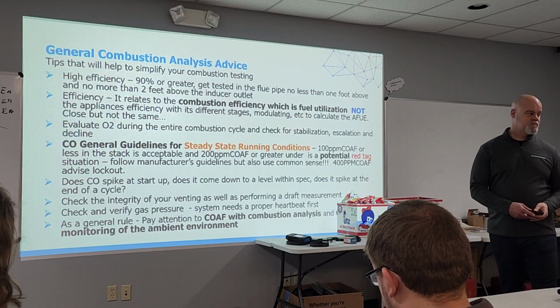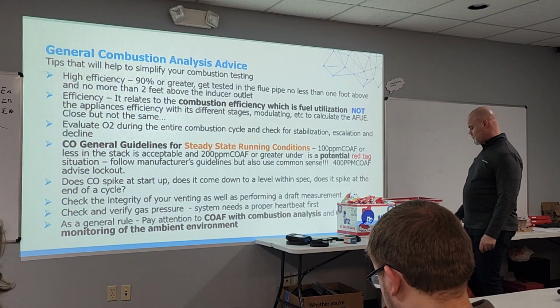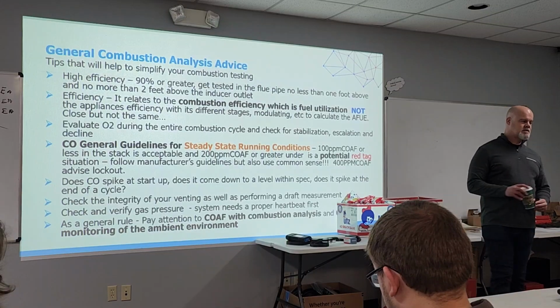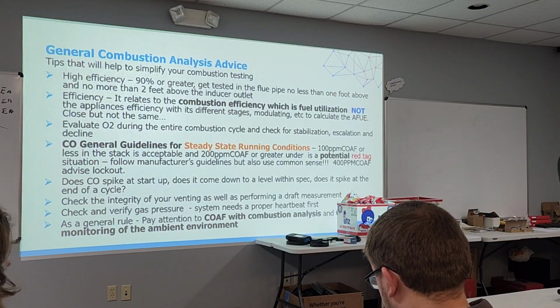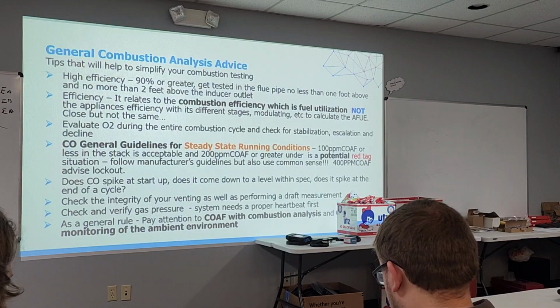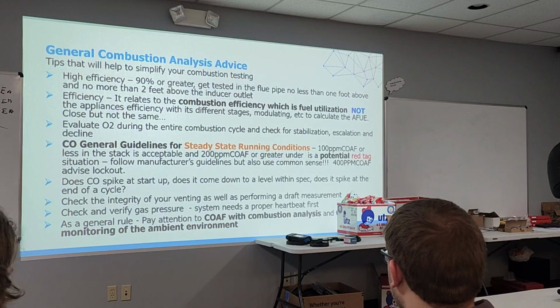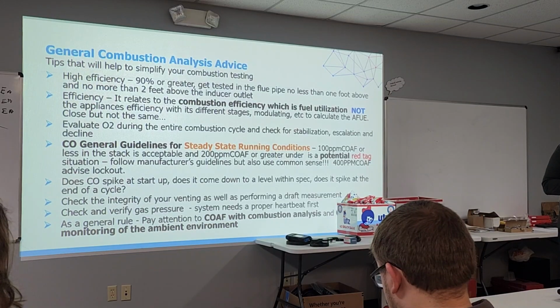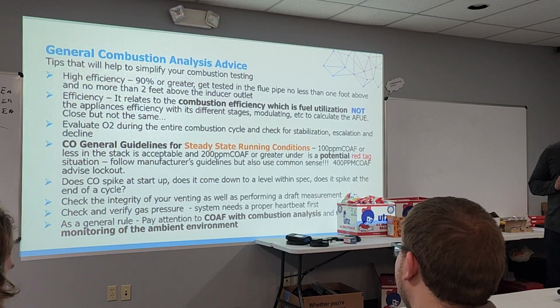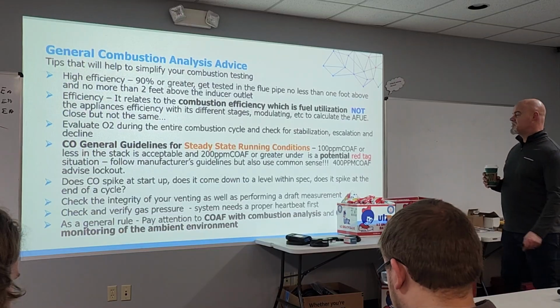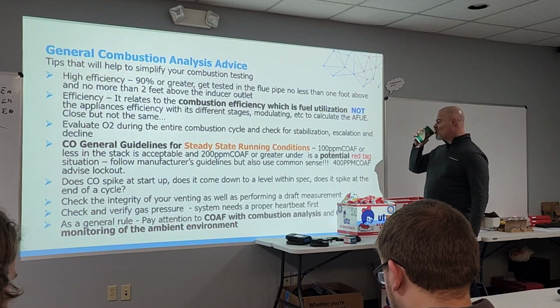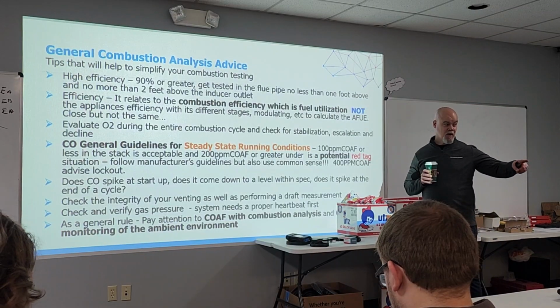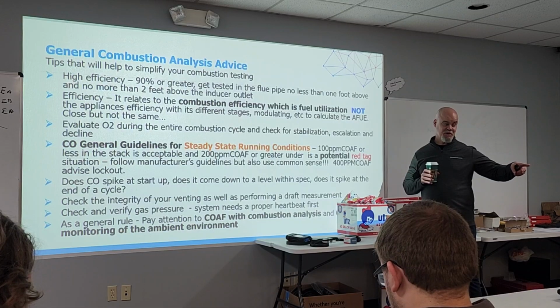Yes. So the CO air free, we take it in the supply ducts or on the stack? You take it on the stack. But I'm going to get to the supply duct stuff later, in the cracked heat exchanger section. So don't blow up my spot. I'm only kidding. That's a very good question though. So it's in the stack. But when I'm monitoring the whole house, that's when I'm using the CO air free.